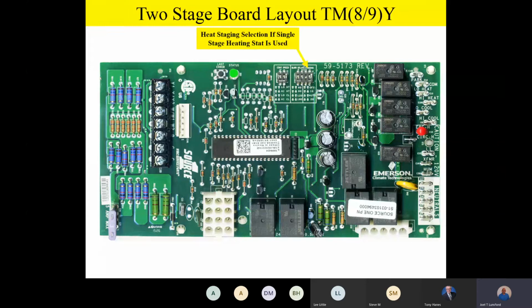So it's really, really important. Now, you do what you want to do, but what I would do if I was in the field and I was stuck with a single stage thermostat is make sure that that was in the auto position and let the board make some intelligent decisions on when to stage. Please write this down or make a note of this. Don't put those dip switches in the off position if you have a single stage thermostat, because you'll never get out of first stage. You'll never have more than first stage heating. So please make a note of that, or a mental note of that.